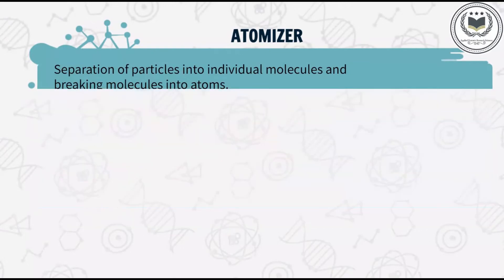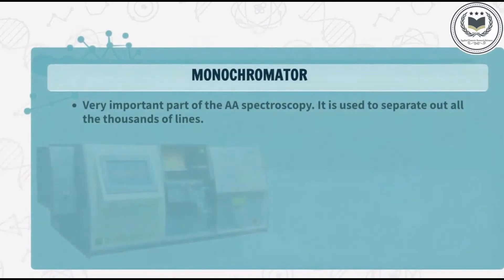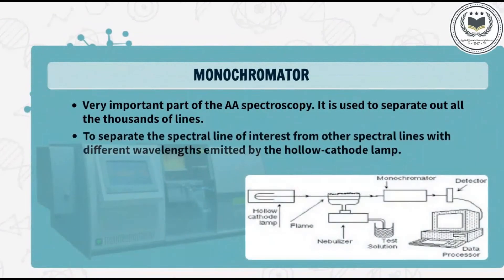The monochromator is a very important part of atomic absorption spectroscopy. It is used to separate out all the thousands of spectral lines. The monochromator is included as an important device in the optical system of an atomic absorption spectrophotometer, and its function is to separate the spectral line of interest from other spectral lines with different wavelengths emitted by the hollow cathode lamp.